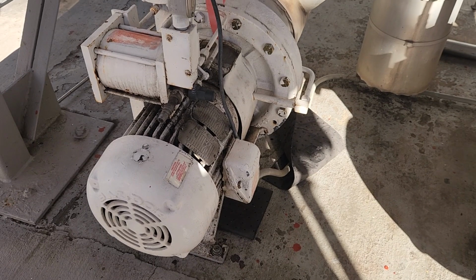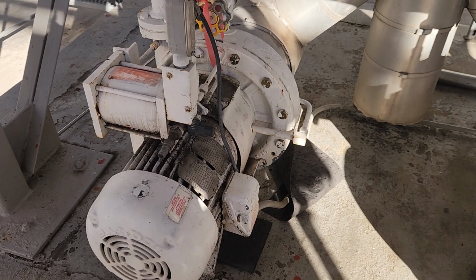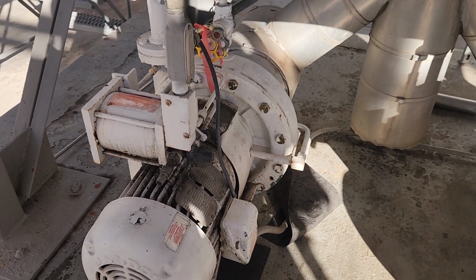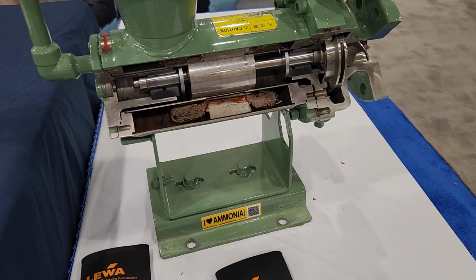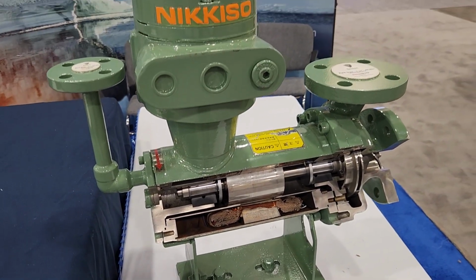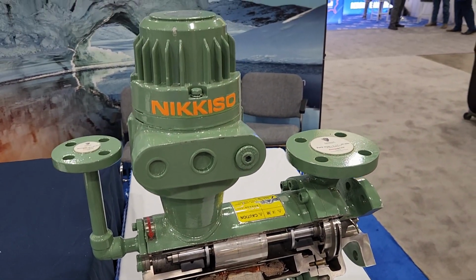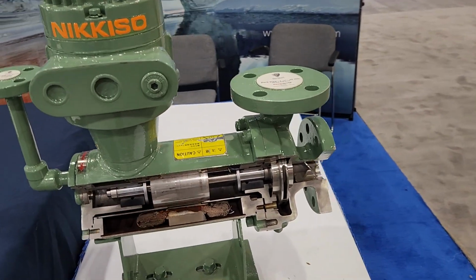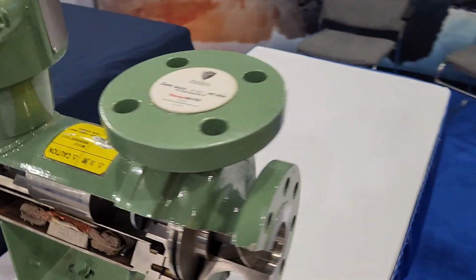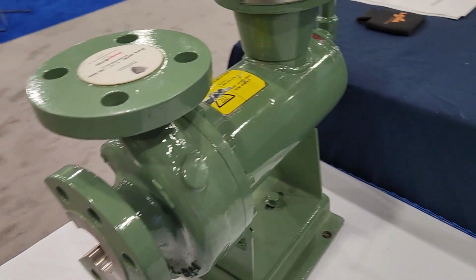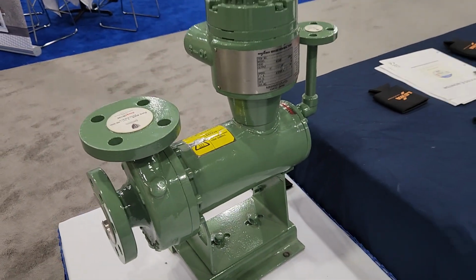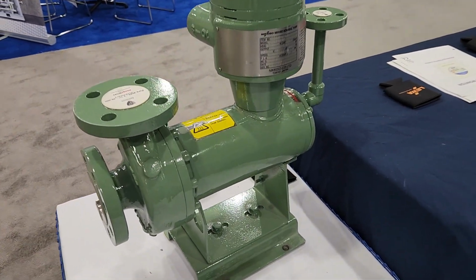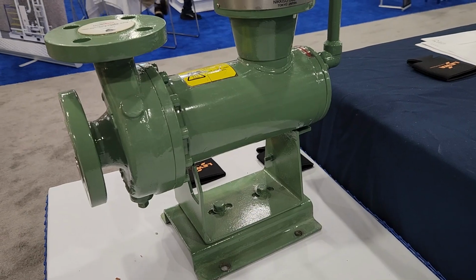Historically, open drive pumps were used. These pumps use a shaft seal that requires lubrication and is prone to minor leaks. To address this, it is now more common to see hermetically sealed pumps used in a system design. A hermetically sealed pump is often called a canned motor pump because the pump and motor are enclosed in a single sealed housing, which eliminates the risk of refrigerant leakage. 2 categories of pumps to be familiar with are the open drive and hermetically sealed pumps.